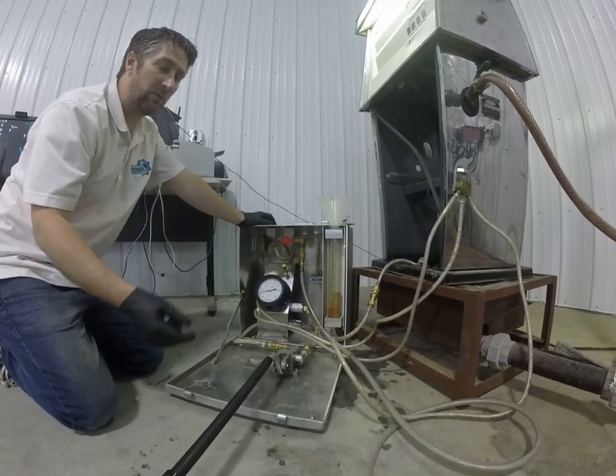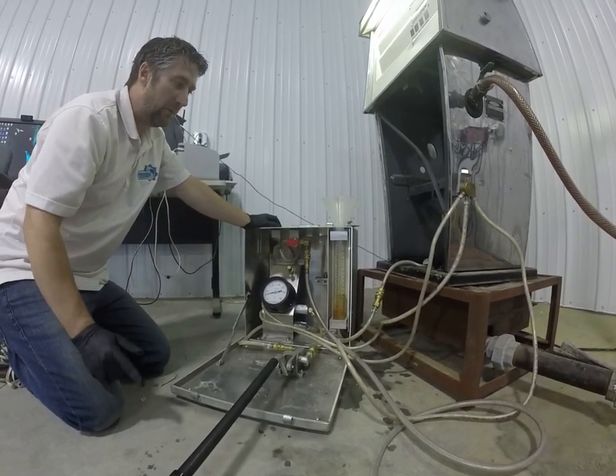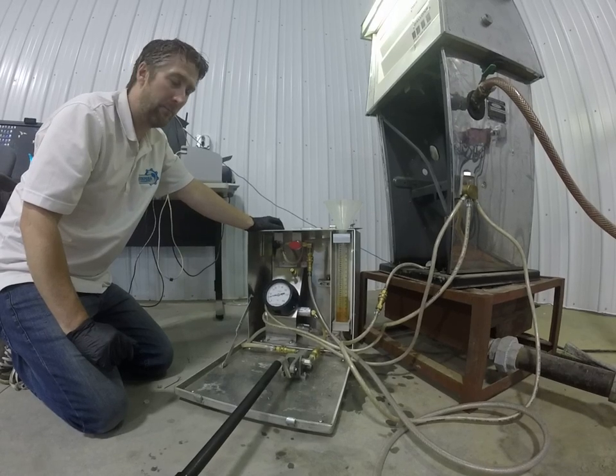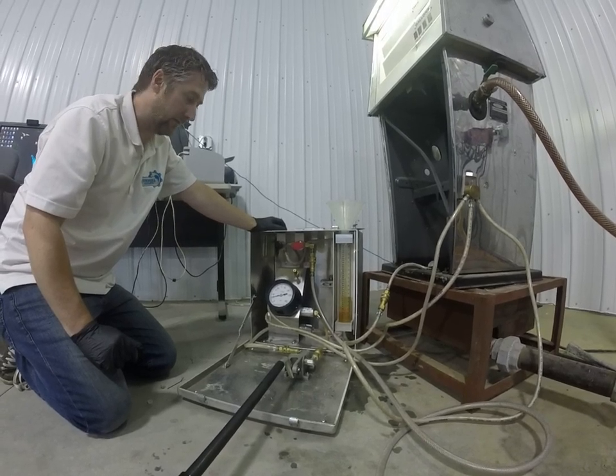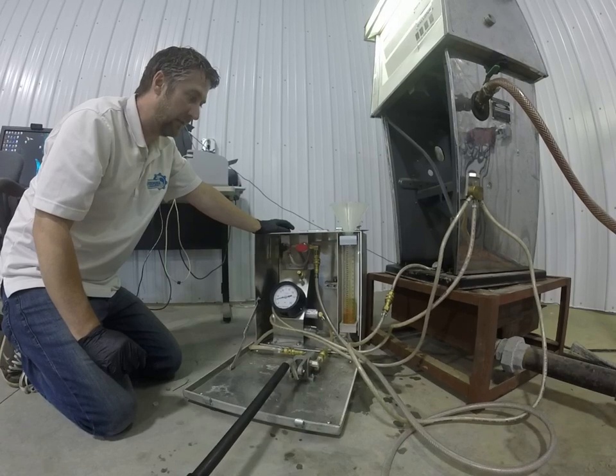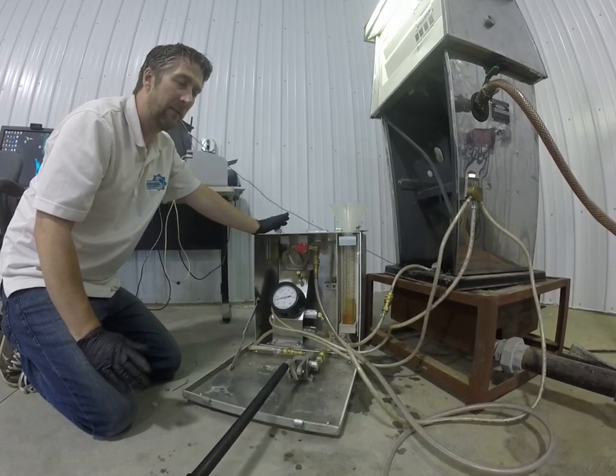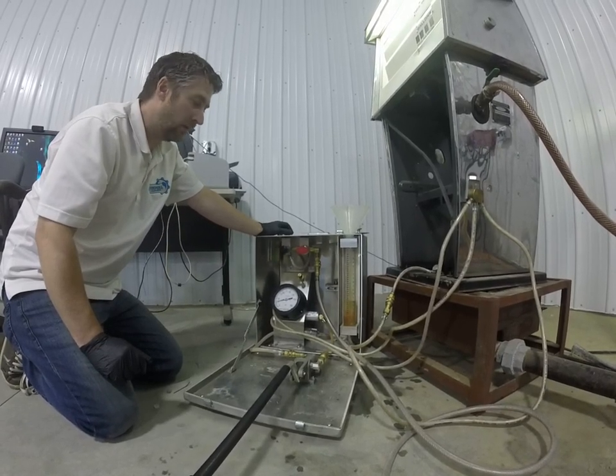If the leak detector goes straight into full flow, we would then go back to the calibration step and make sure that the calibration is correct. If we do that 2 consecutive times and it fails both times, it's because the leak detector is bad.